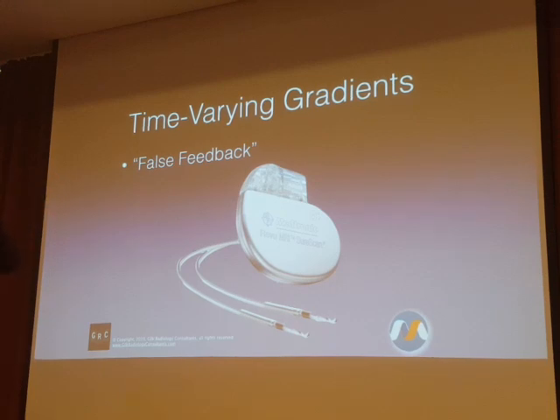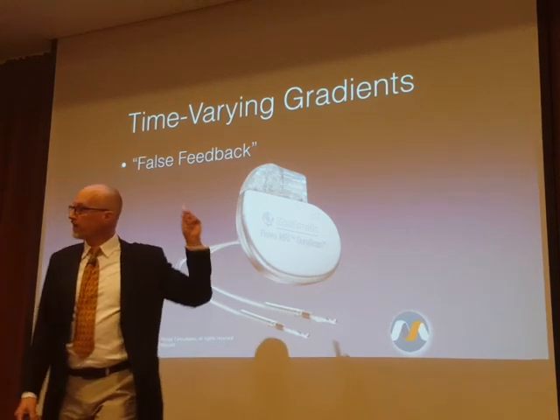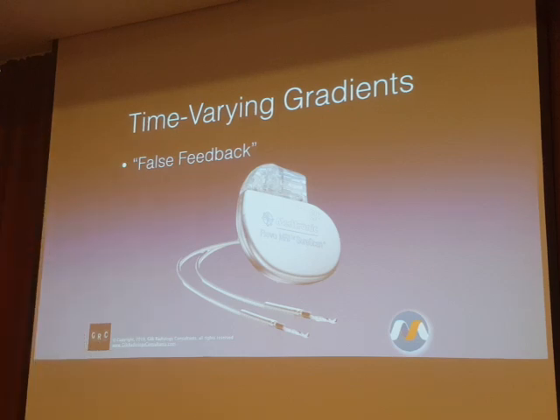Time-varying gradients produce electromagnetic fields at rhythms. There is the potential that a pacemaker or another biostimulation device that actively monitors based on electrical signals may perceive the time-varying gradients as a seriously out-of-range biological function. If the pacemaker all of a sudden thinks that your gradient, which is firing at 200 times per second, is your heartbeat, the pacemaker may fire and try and recapture that rhythm. The pacemaker will try and fire at whatever the aberrant rhythm is, and then slow it back down or speed it up to where it's programmed to leave that patient.